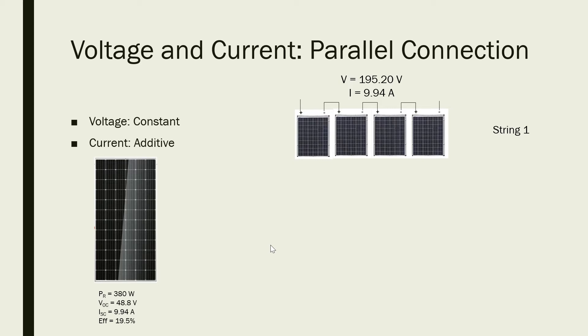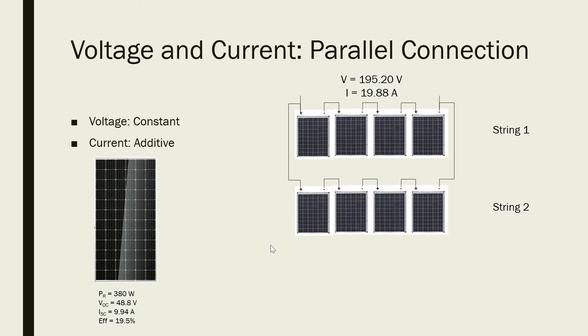We call this string number one. Suppose we add another string — another set of solar panels connected in series — and connect that in parallel to string number one. As we have said, the voltage is constant, so the voltage across this solar panel array didn't change; it's still 195.20 volts. But the current is additive, so before it was 9.94 amps, and connecting another string makes it 9.94 times 2, which is 19.88 amperes.